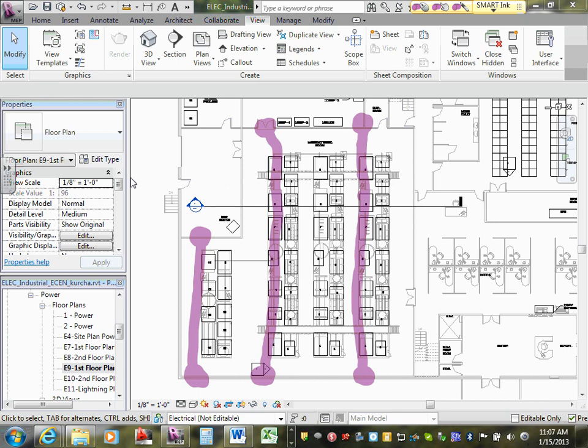Typically we try to make it as aesthetic as possible. But we have to be at least 3 feet away from any diffuser or grill. We have to be at least a foot away from any light fixture. So when we're installing all our devices, we have to look at what's going on. We try going one way or the other. You should be able to have a clear path.